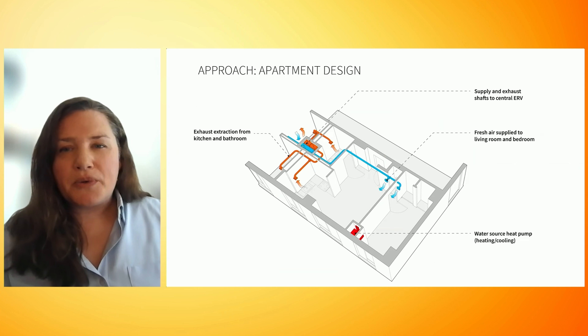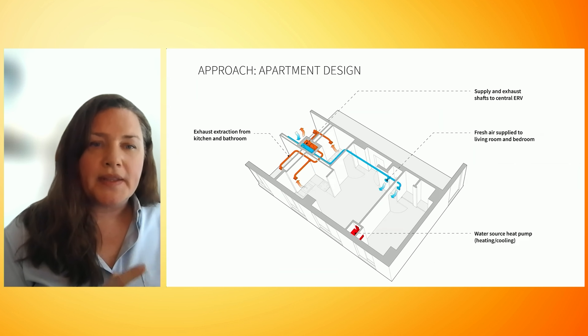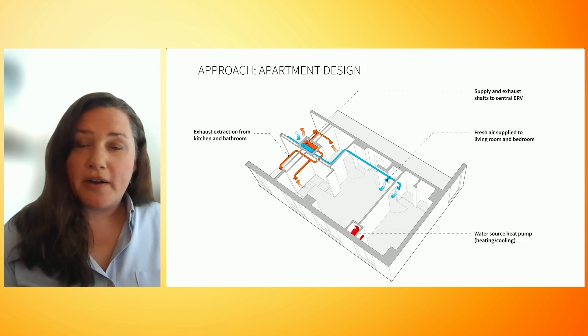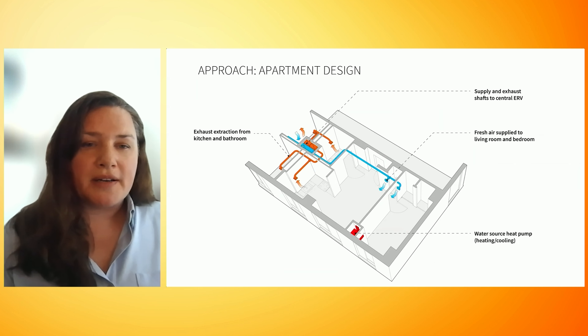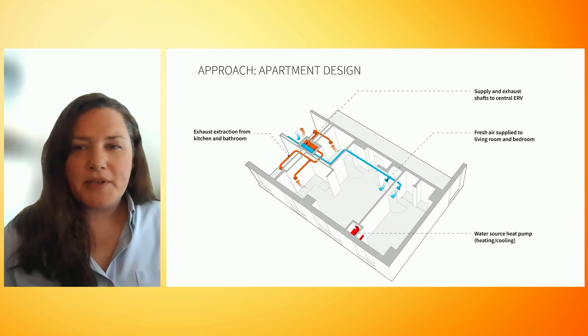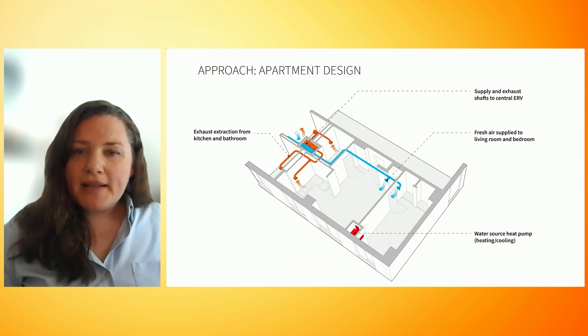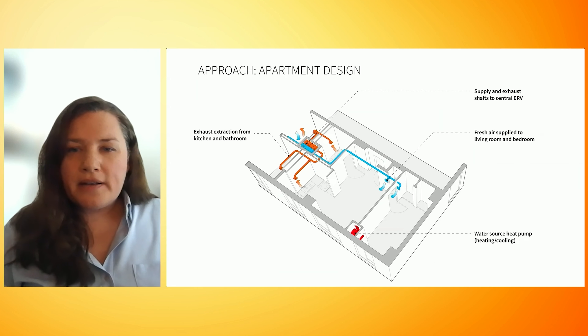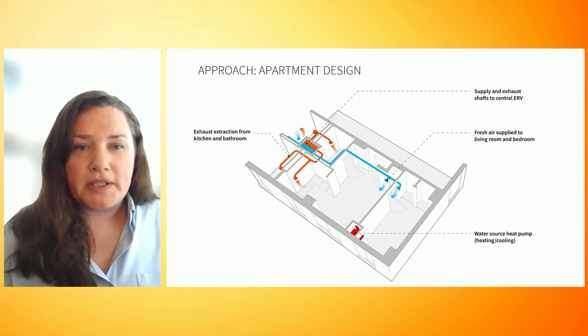It's important to note that the heating and cooling system is entirely separate from the ventilation system. Ventilation is provided with a central ERV on the roof, connected to the ductwork in the apartment, as shown here. For architects, when coordinating with your MEP engineer, it's helpful to keep these two functions separate conceptually. Sometimes you can combine them, but it's rare in our typology for economical passive house multifamily projects of this size.